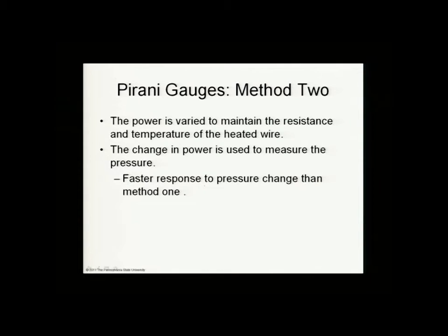Another type, it's the same sort of thing. Again, it's looking at what it takes to keep the resistance the same, or the temperature the same as the heated wire, and then you change the power. Basically the same thing. You either change the power, you change the current, or you keep the currents the same and look at the voltage. But in general, you're looking at change in the resistor temperature that's caused by the gas molecules taking the energy away.